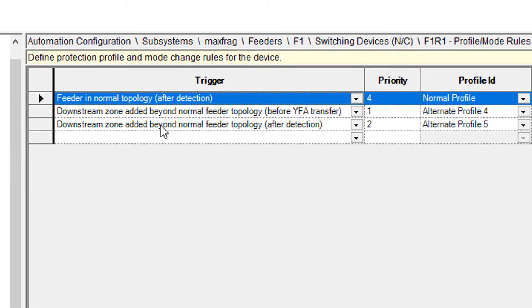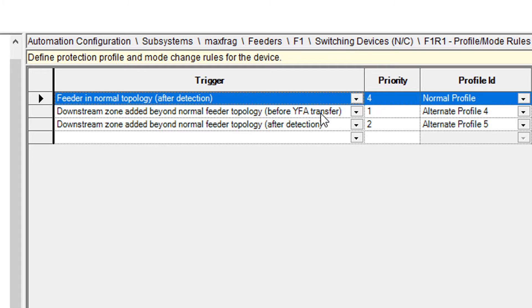If YFA is going to add a zone beyond the normal feeder topology, and if YFA knows it's going to do that before it does that, it will transition to alternate profile number four. Alternate profile number four is going to show up as a five on the diagram.